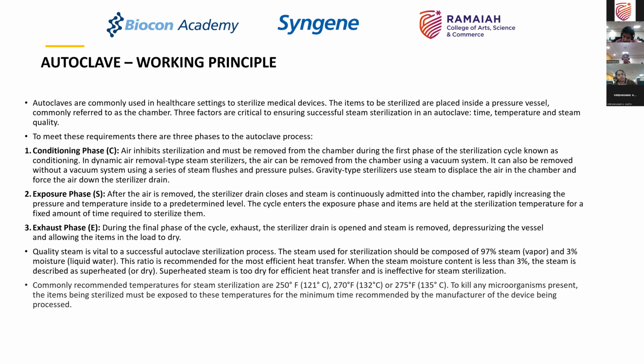So the three broad phases under which an autoclave operates start with the conditioning phase, where you remove the air either by using a vacuum as a means, or by allowing the steam to displace the air.